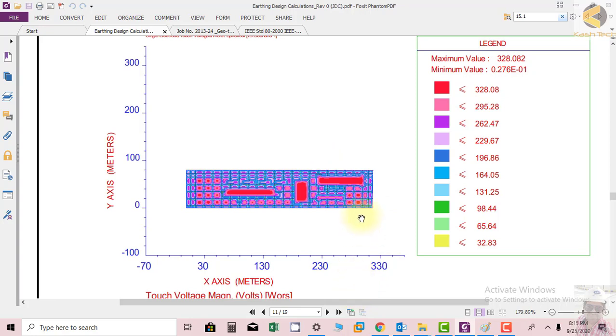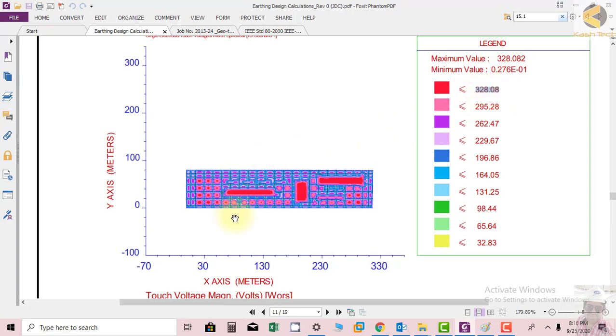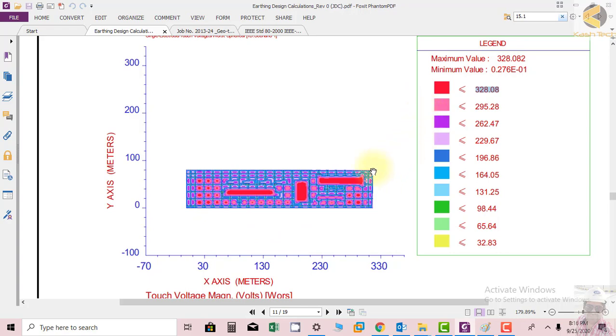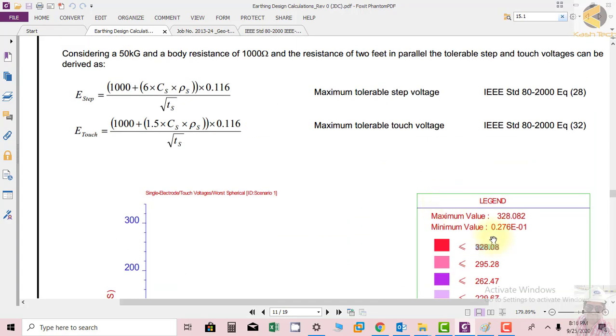The maximum voltages are shown in red color which is 328, which is really less than the allowable maximum touch potential in the substation. In the substation different areas there are different touch potentials, but the maximum touch potential is less than the tolerable touch potential. So let's see.